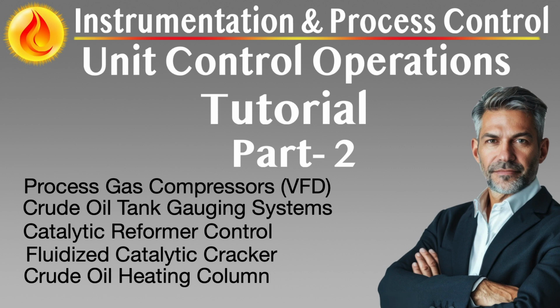Emissions and environmental controls have become deeply embedded into FCC operation. Regenerator flue gas is closely monitored for NOx, CO, and particulate emissions using inline analyzers. Emission control devices such as electrostatic precipitators, ESPs, CO boilers, and selective catalytic reduction, SCR, systems are managed with feedback from these analyzers. Control logic adjusts combustion air distribution, catalyst additive injection, e.g., NOx reduction additives, and flue gas temperature to maintain emissions within regulated limits while preserving regeneration efficiency.